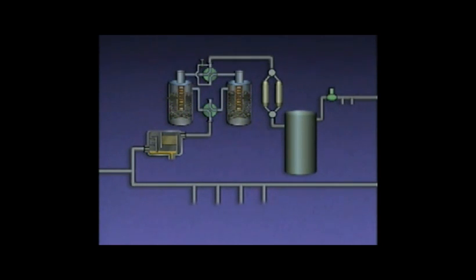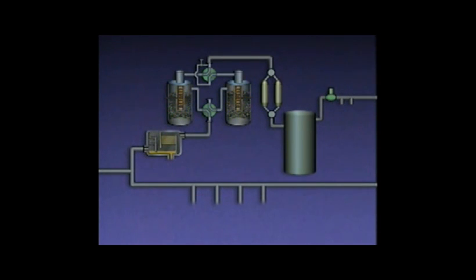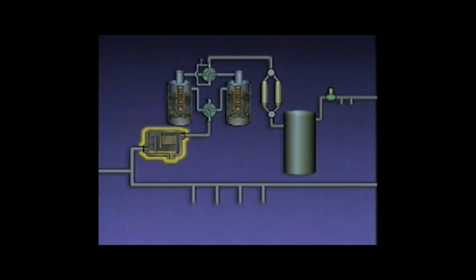Pneumatic instruments require compressed air that is extremely clean and dry, and at a lower pressure than the air supplied by the plant air header. Providing this quality of air requires devices such as an oil separator, a desiccant dryer, filters, and a pressure reducing valve. A small amount of oil is frequently present in the air discharged from a compressor, and since this oil can damage control system components, it must be removed. This function is carried out by an oil separator.